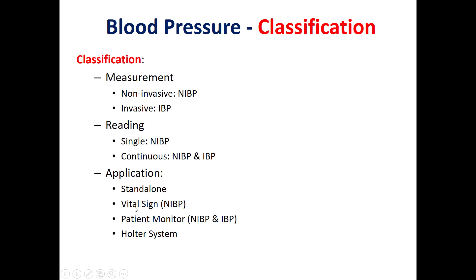For example, the vital signs monitor includes non-invasive blood pressure, temperature, and pulse oximeter readings. Another device is the patient monitor, which includes invasive and non-invasive blood pressure, electrocardiogram, pulse oximeter, temperature, CO2, and many other parameters. Blood pressure can also be used in a Holter system, which records blood pressure non-invasively over a long period — for example, one day or more.